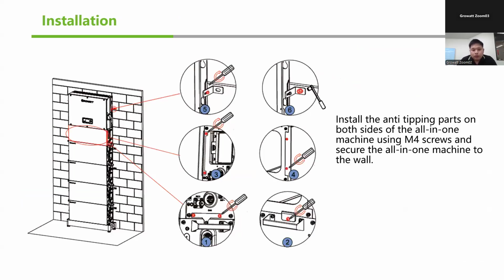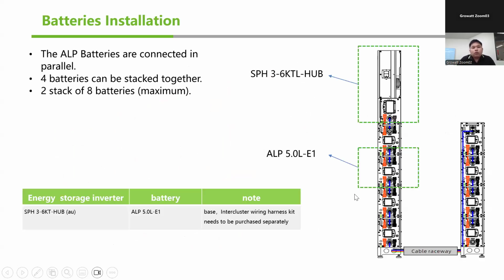Oh yeah, before I move to the next one, if the installation is at ground level, you can also install the inverter directly from the ground, but if you do, be sure to include the base plate at the bottom to avoid direct contact between the batteries and the ground. For battery installation, like I mentioned earlier, 4 batteries can be stacked together, and it will provide up to 2 stacks of batteries at maximum. And these batteries can be connected in parallel.